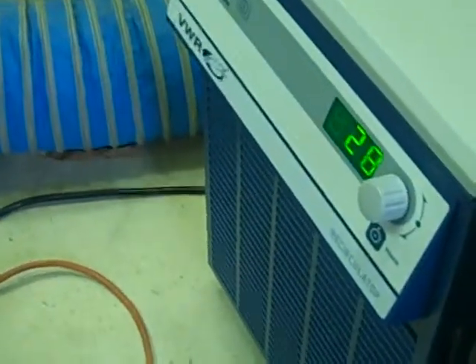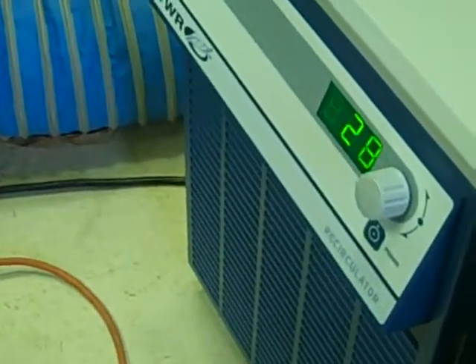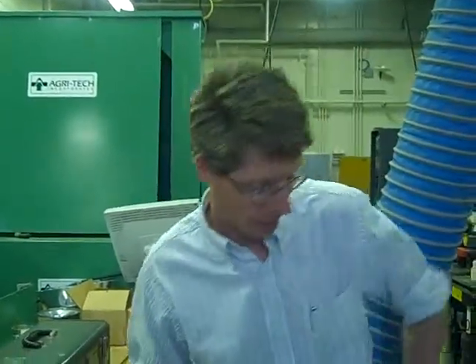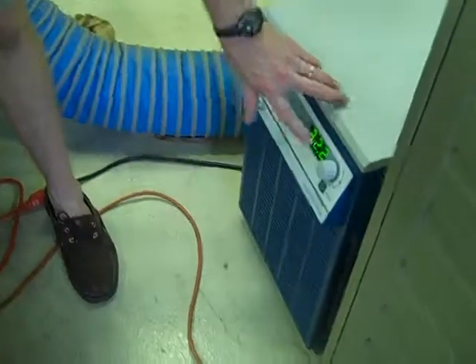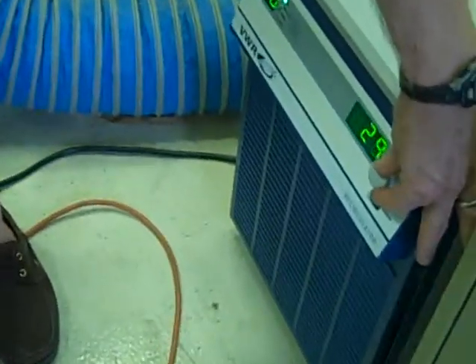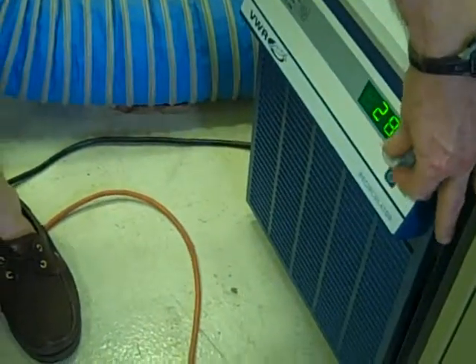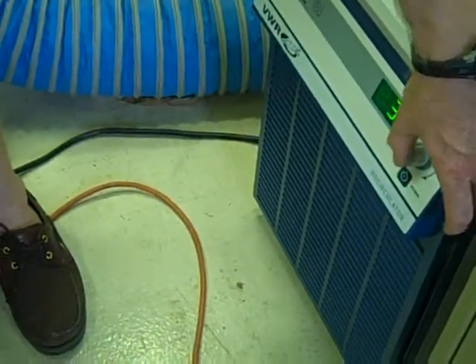It'll start up and show you the set point, and after a couple of seconds, it'll show you the actual chiller temperature. So the actual chiller temperature is at 31.9. If you're just going to be hanging out for a while, not starting right away, set the chiller at about 34 so it doesn't freeze up. To change the chiller temperature, you press the knob in and then spin. So for example, if we were going to go on standby, we'd go up to 34 and press it again.